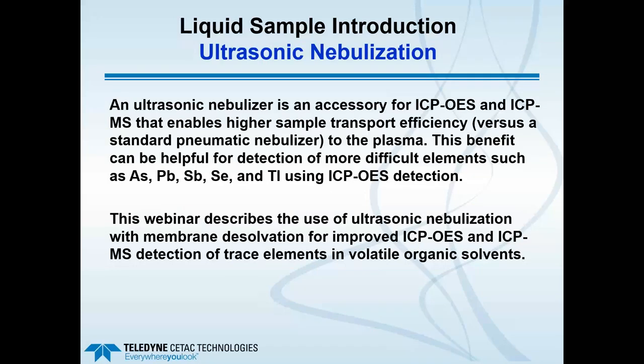The ultrasonic nebulizer is largely an accessory for ICP-OES and ICP-MS that improves sample transport efficiency versus a standard gas-based pneumatic nebulizer to the plasma. This can be very helpful for detection of more difficult elements, especially arsenic, lead, antimony, selenium, and thallium when using ICP-OES detection. We're going to describe the use of the ultrasonic nebulizer with a membrane desolvator for detection of trace elements in volatile organic solvents, versus solely aqueous samples such as drinking water or wastewater.